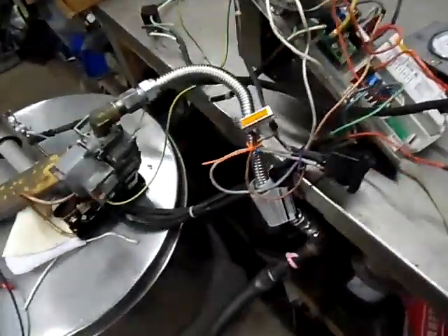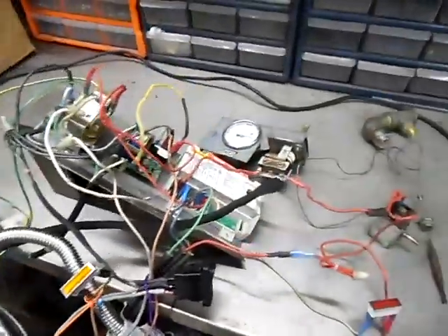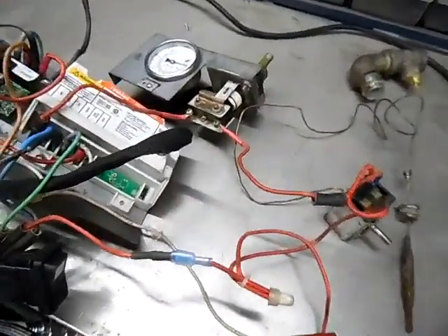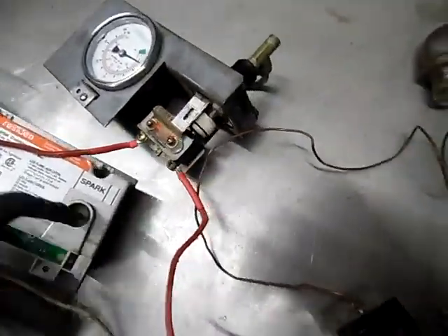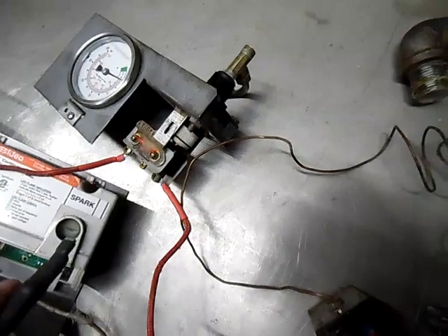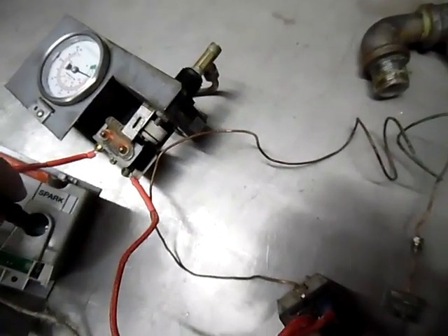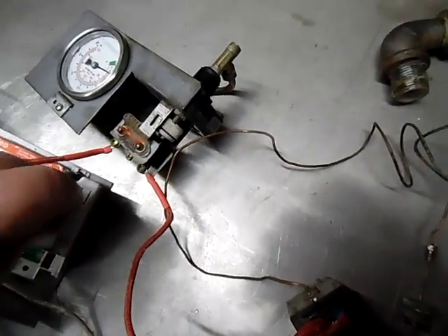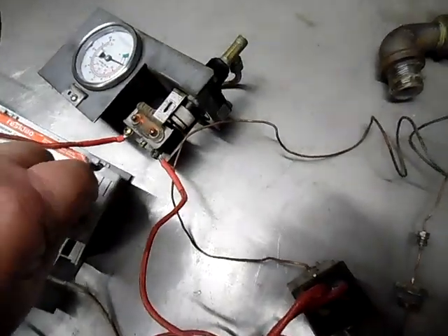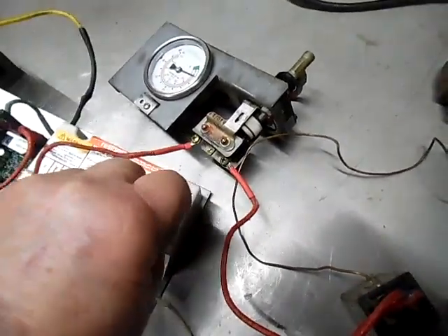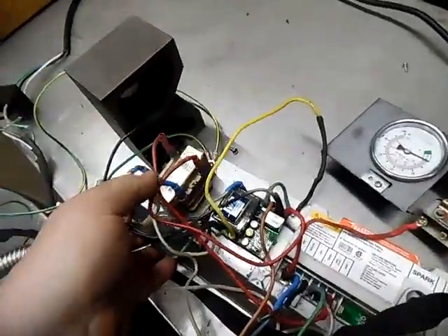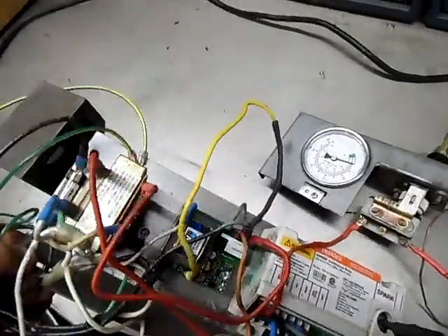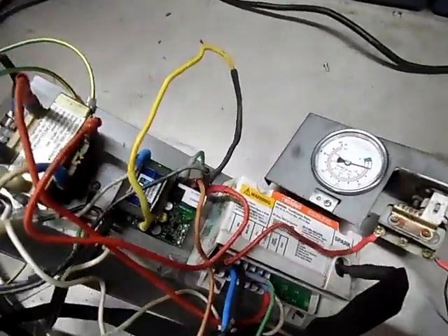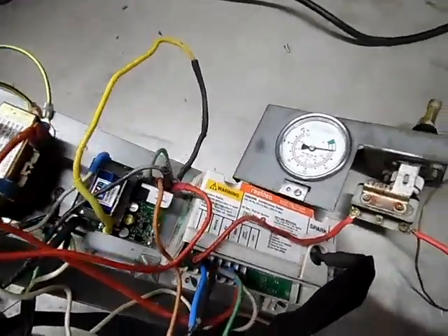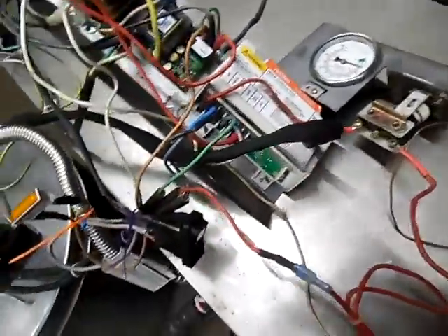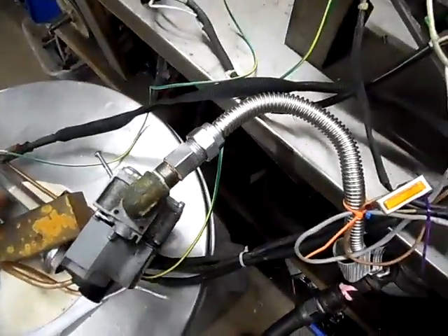One major thing I want to show that we've come up with recently is the spark plug wires. We actually did it to ourselves. We bought spark plug wires from another source, not thinking about it. These are solid core wires, single rod. The problem with the single rod system, it's very touchy of reading the sense. You don't have a second rod to read the flame. So that spark plug wire is also acting as your wire to read the flame sense when the flame comes on.